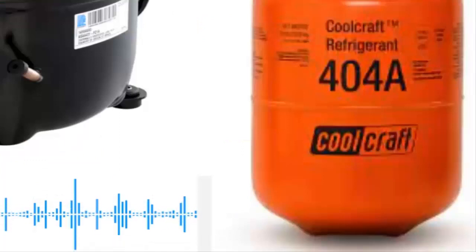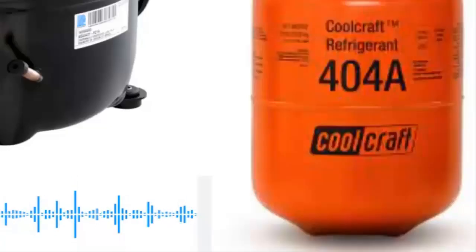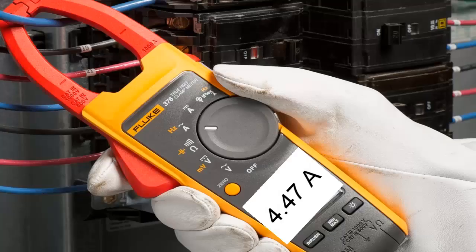The half-HP compressor using 404A typically operates with polyolester type oil, with a quantity close to 350 milliliters and often with ISO 22 viscosity. With a voltage between 115 and 127V, the regular current consumption of this compressor is around 4.47A. For a voltage of 220V, the consumption is approximately 2.54A.